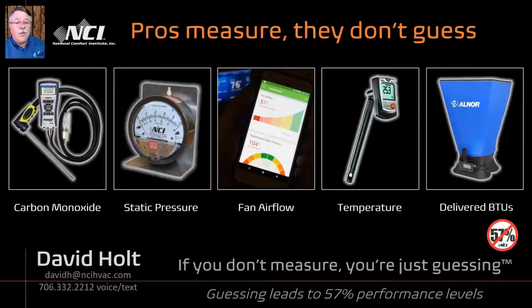It'll run at 1 inch of static pressure when it's rated to design at 1/2 inch. Right on the nameplate it says maximum total external static pressure, 1/2 inch. We had it running at 1 inch, and it was the equivalent of seven 100-watt light bulbs worth of energy being consumed just by the blower. And guess what it's supposed to operate at? Less than a 100-watt light bulb.